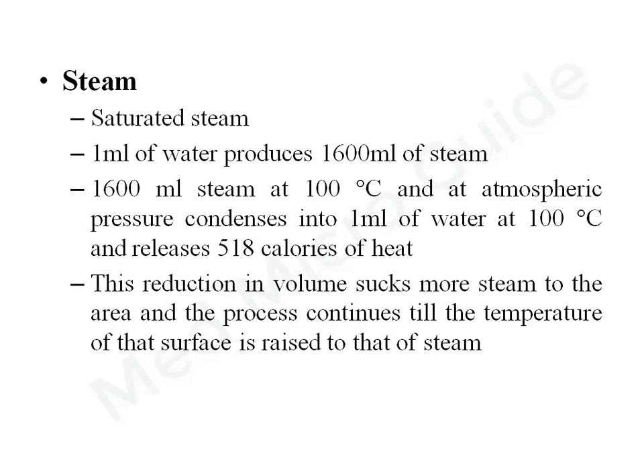There are three types of steam: wet steam, saturated steam, and superheated steam. Saturated steam is the ideal steam for sterilization by moist heat.